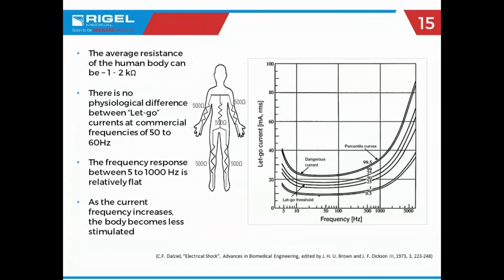And this shows the body model, the frequency. So this is why when we talk about electrosurgical generators, those are running at 350 kilohertz. So the muscles can't respond to that frequency. You see that's where it starts to fall off right around here. And that's why they use the high frequencies for doing electrosurgery.